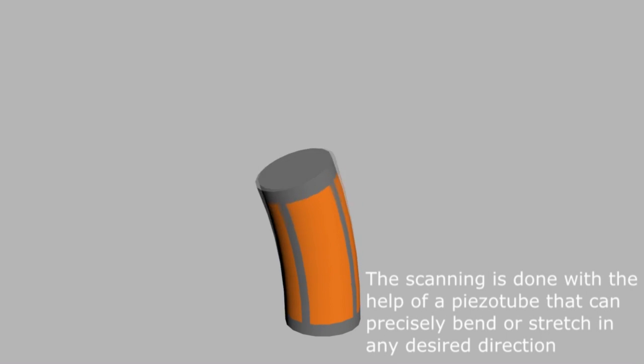The surface is scanned with a sharp tip, with the help of a piezo tube, which can bend or stretch depending on the electric potential supplied.